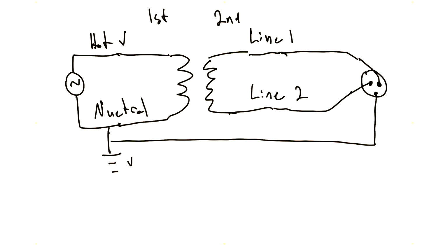So what does that allow me to do? Well, if a person were to touch line 2 or something that is at the same potential as line 2, such as a medical device or other, they're absolutely fine because there's no path for current to go through the person. There is no path to a lower potential. So what ends up happening is this isolated system ends up having line 2 at the same potential as the person, whatever potential they might be at.